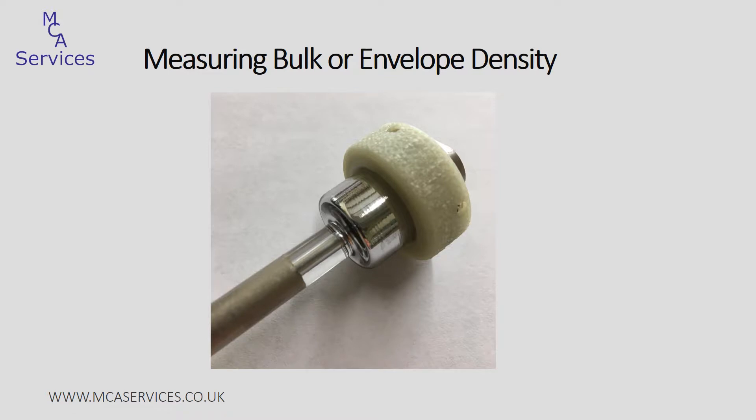At the end of the low pressure analysis the penetrometer is now filled with mercury and we'll weigh it again at this stage. The various masses — the sample mass, the mass of the assembled penetrometer without mercury, and again with mercury — are all entered into the Autopore software and the bulk density of the sample is calculated automatically.